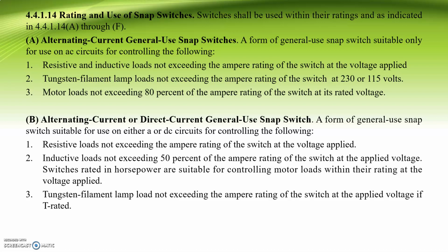Chapter 4.4.1.14, rating and use of snap switches. So switches shall be used within their ratings and as indicated in chapter 4.4.1.14a through F. So A, alternating current general use snap switch, a form of general use snap switch suitable only for use on AC circuits for controlling the following. So first, resistive and inductive loads not exceeding the ampere rating of the switch at the voltage applied. And the second is tungsten filament lamp loads not exceeding the ampere rating of the switch at 230 or 115 volts. And the last, motor loads not exceeding 80% of the ampere rating of the switch at its rated voltage.